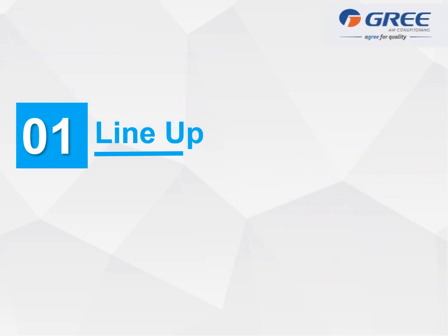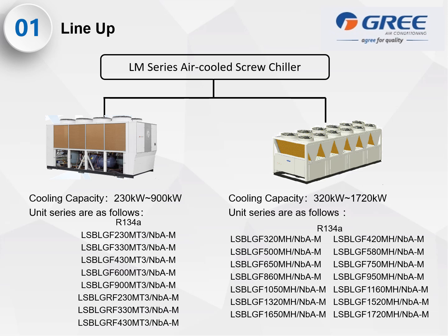For the lineup, the LM series air cooled screw chiller ranges from 230 kilowatt to 1720 kilowatt. 230, if you divide it by 3.516, that's about 65 TR. And 1720 is about 489 TR. So if your development is a hotel or small capacity but varying in loads, I believe screw chiller is the best.